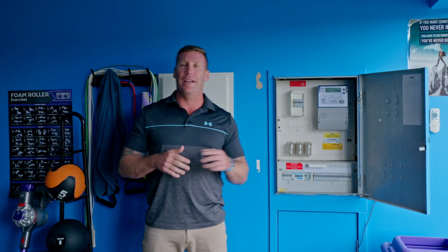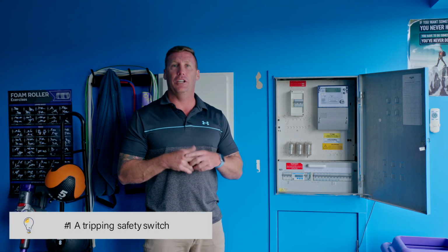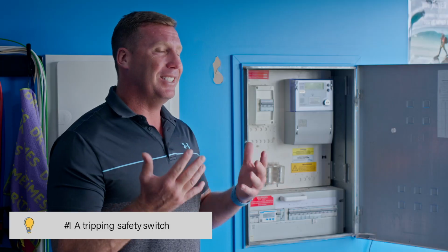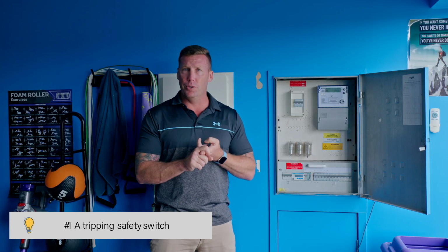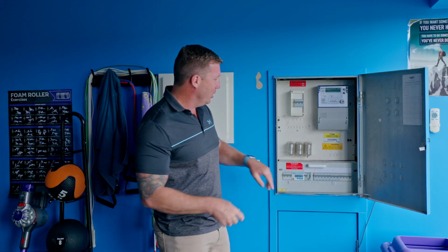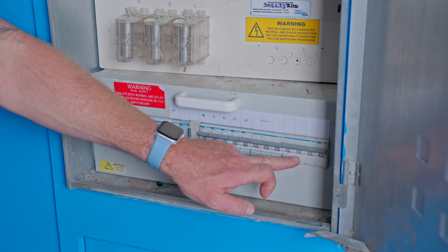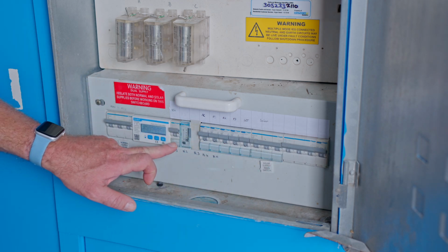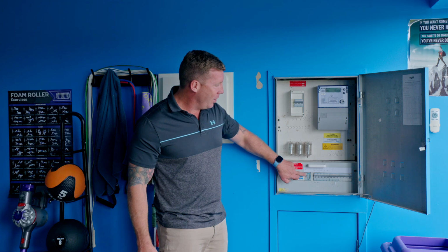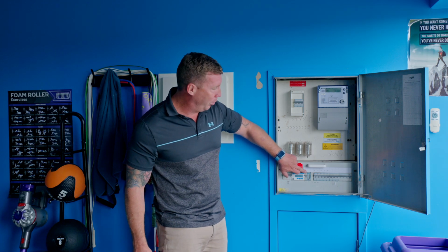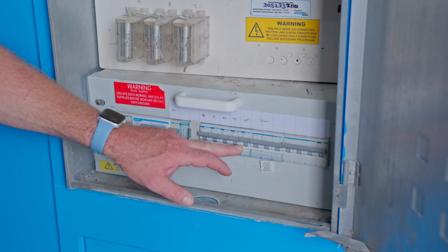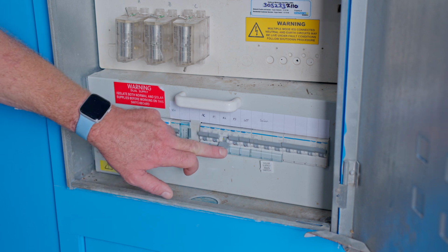The most common call out we get on a weekend or at night time is a tripping safety switch. A safety switch is different to your fuse or circuit breaker. A common circuit breaker is something like here, or here, a 3-phase one, or a single one there. Notice it doesn't have a little blue push button, some are gray, whereas this one here, if I trip it and press that button, it trips down. That's your safety switch. This one's a combination safety switch circuit breaker, meaning it's a combined one.